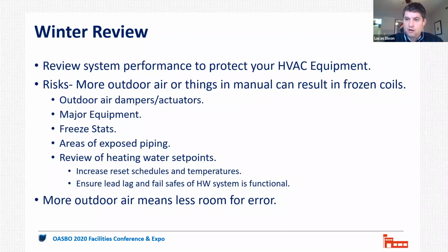Yes, on that annunciation part, it's a really good time to check to make sure that your building automation system has outbound alarms for pump, boiler, and freeze-stat trips, that they're being sent out, either text-based if your system allows that, or email, or if your system does not allow that, how are you going to have a practice of going in and checking your alarms on a more frequent basis, especially as we're coming into the cold period of the year. When we get the first 10-degree night or sub-zero night, when we're really going to expose those weaknesses, set up with your team a protocol where people are checking in several times that night into the system.